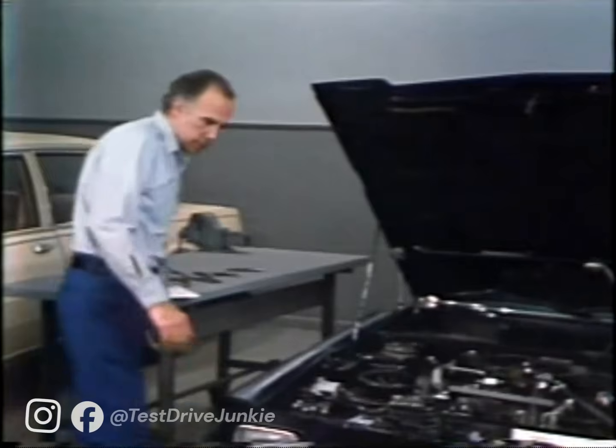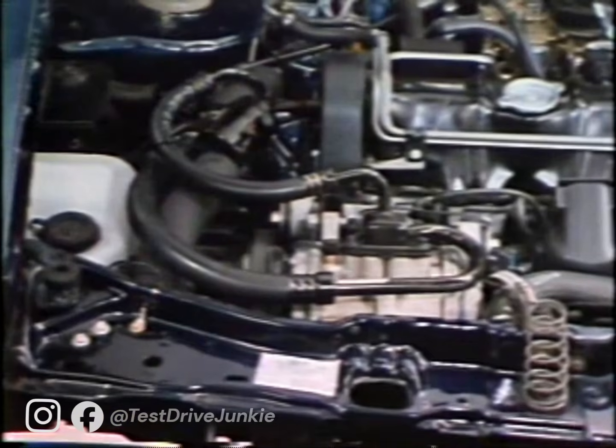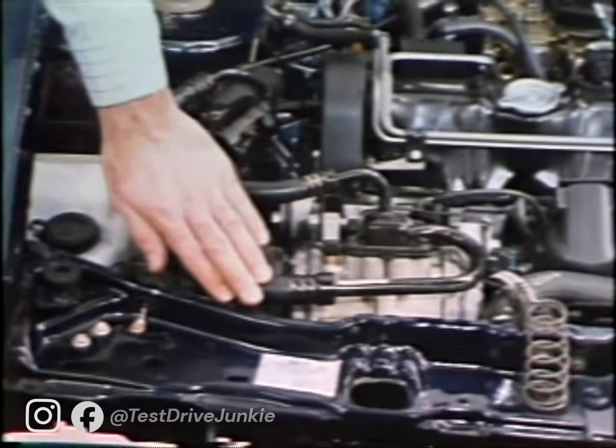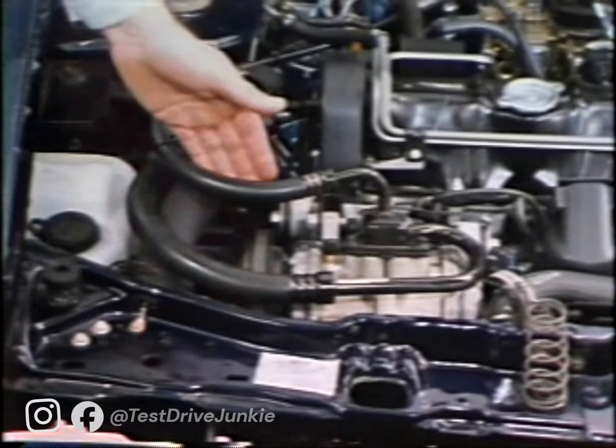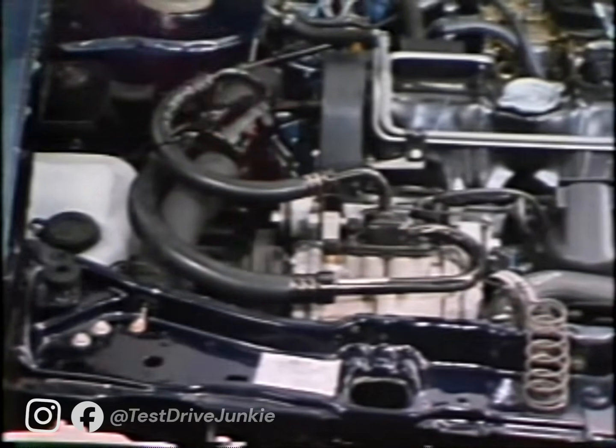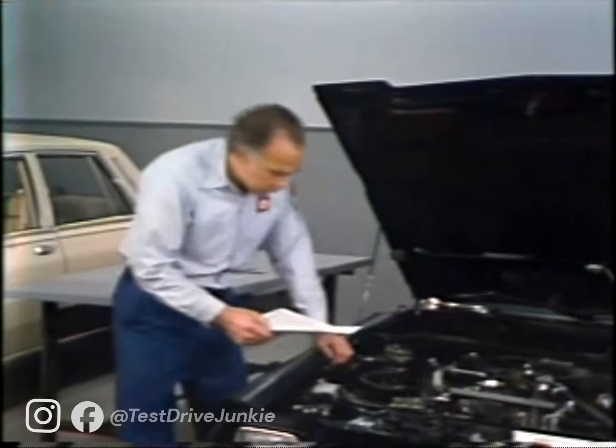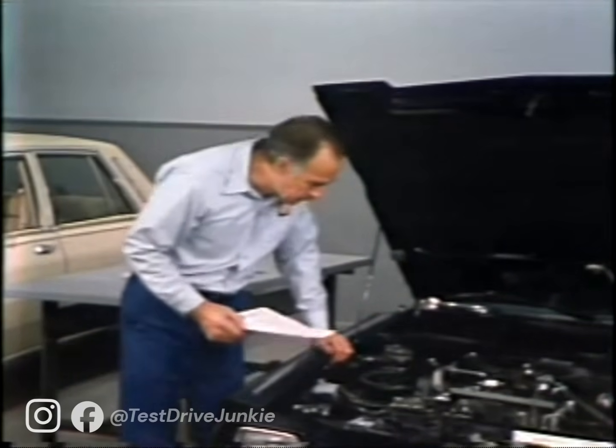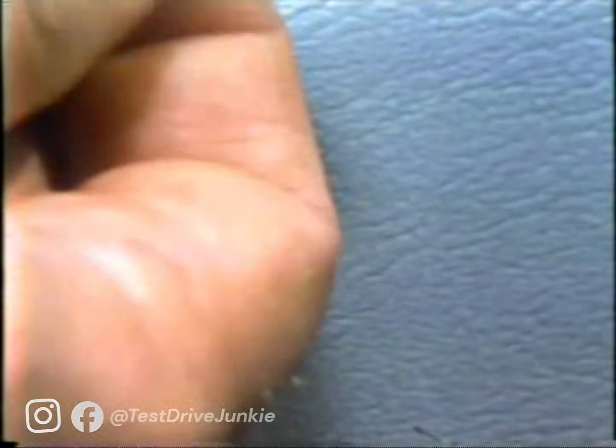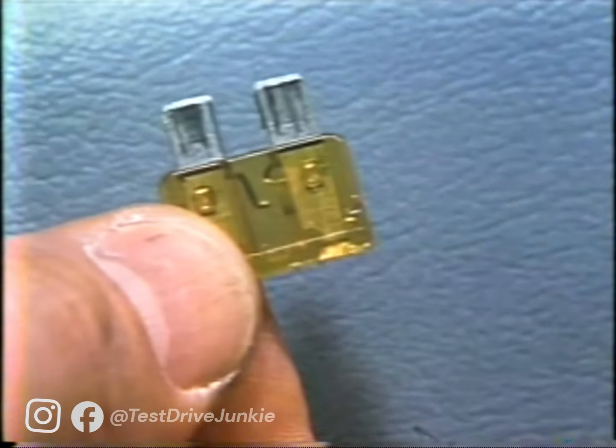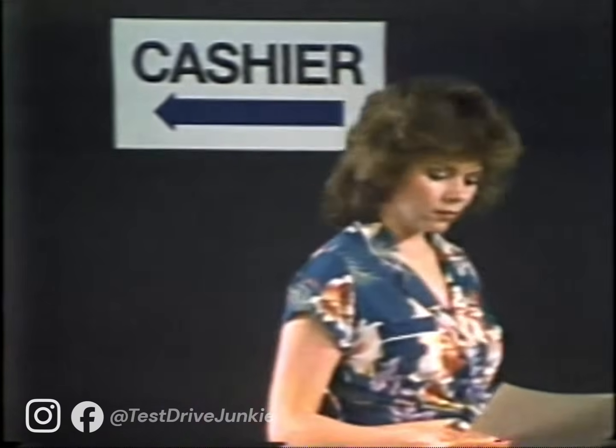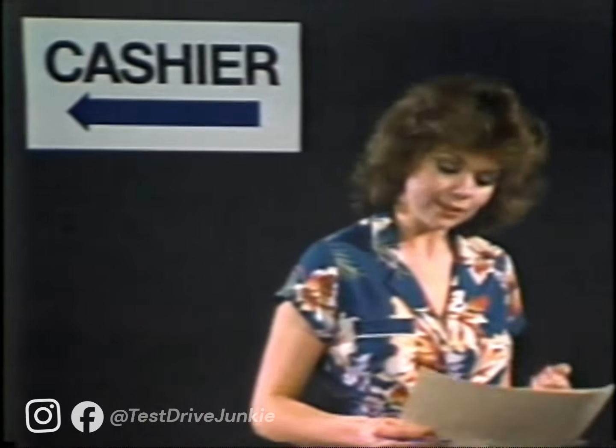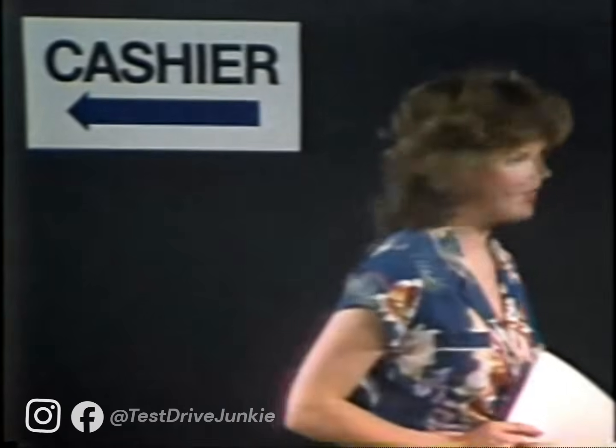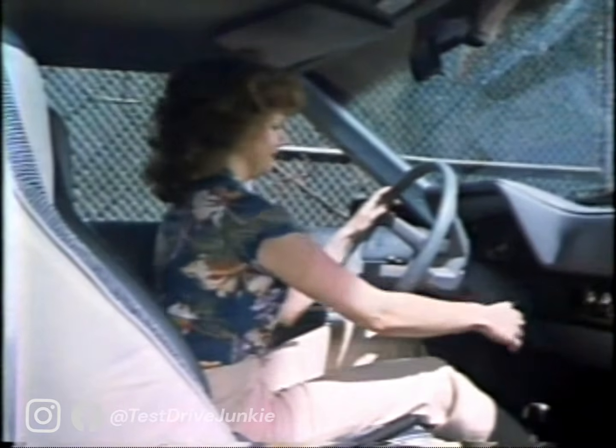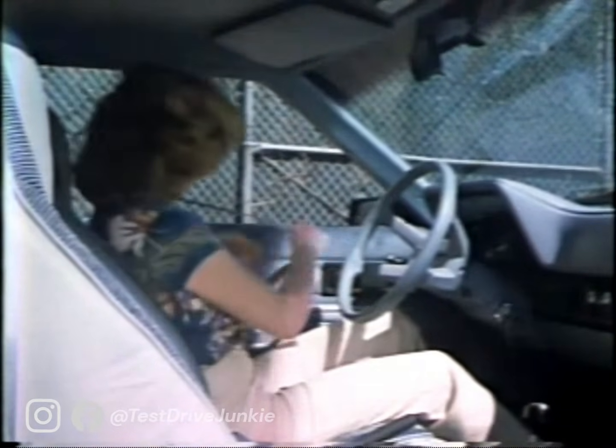For the final AC operation checks, feel the suction line to see if it is cool to the touch, and the liquid line to see if it is warm. Both lines are okay, which completes the AC operation checklist. In this case, we've pinpointed the cause of the customer complaint and corrected it without connecting a gauge set to the system. Be aware that many AC conditions can be corrected by making these simple visual checks.